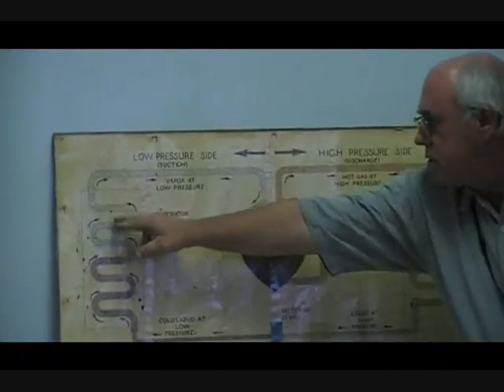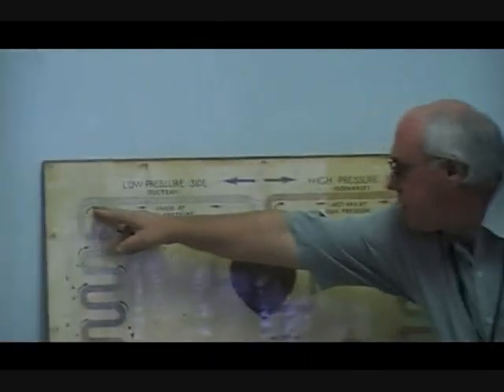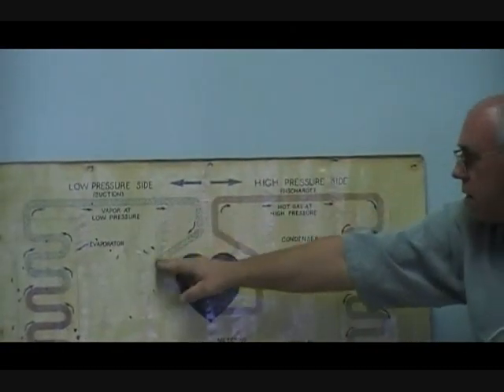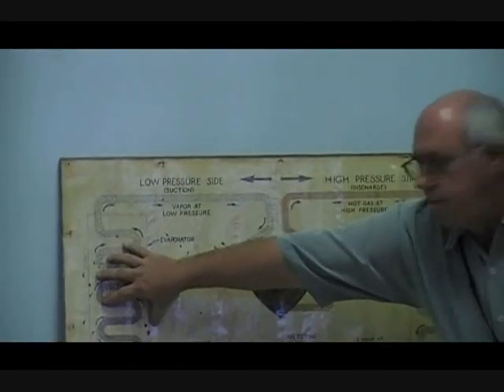It's under low pressure — it's all gas. We use the last pass or two to ensure that we have superheat, which is above the boiling point. The low-pressure gas enters the suction line and returns to the compressor as a superheated low-pressure gas. So what did we really do? We picked up heat from over here and we put it over here.